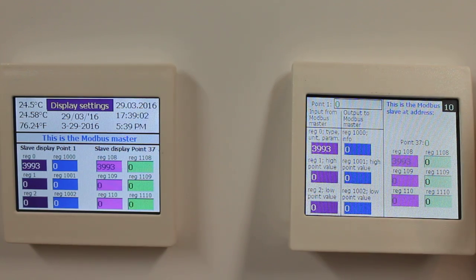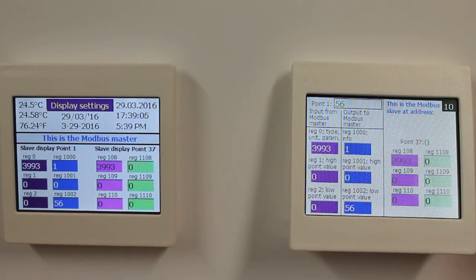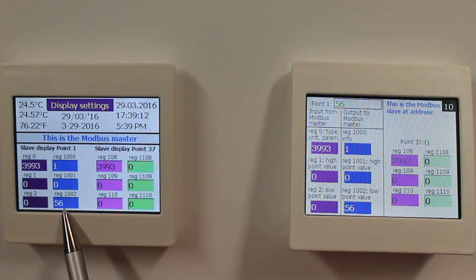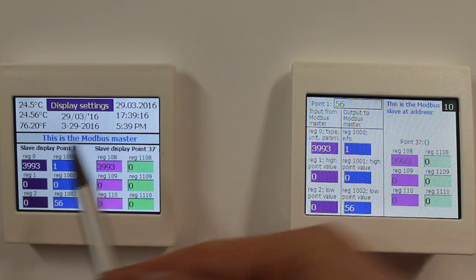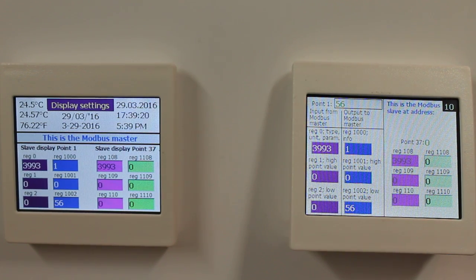When I now change the value of Point 1 on the slave display and enter 56, you can see that this value is read by the Modbus master and the info register is set to 1, indicating to the Modbus master that there has been local user input.